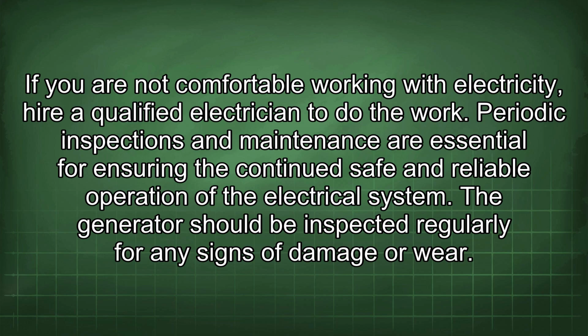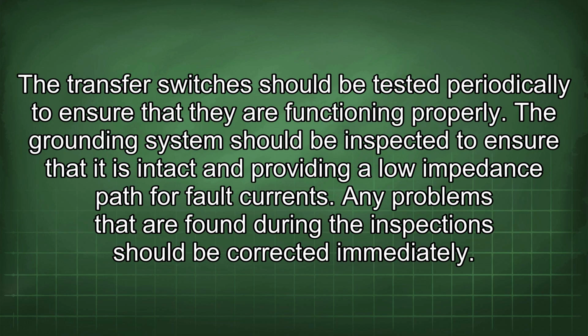Periodic inspections and maintenance are essential for ensuring the continued safe and reliable operation of the electrical system. The generator should be inspected regularly for any signs of damage or wear. The transfer switches should be tested periodically to ensure that they are functioning properly. The grounding system should be inspected to ensure that it is intact and providing a low impedance path for fault currents. Any problems that are found during the inspection should be corrected immediately.